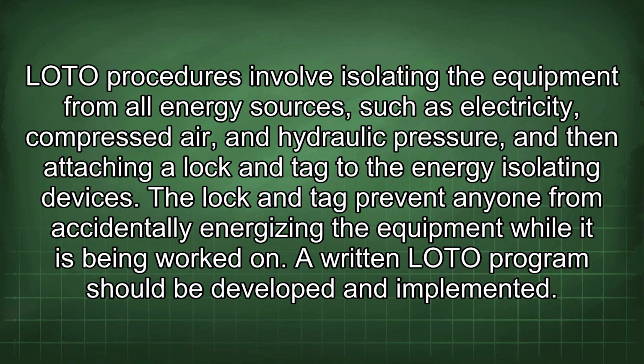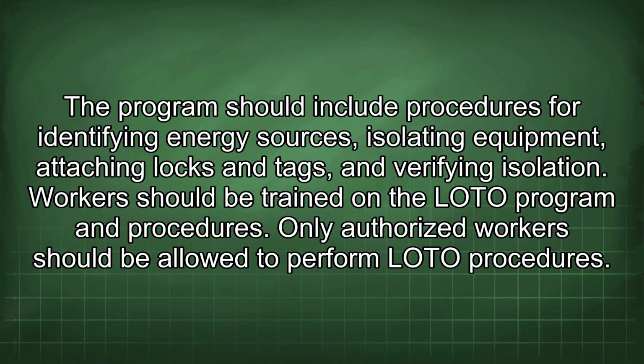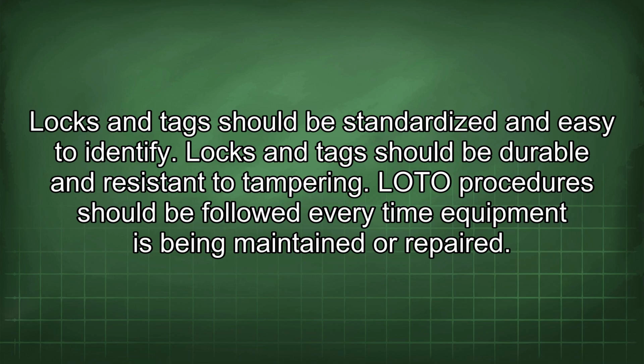A written LOTO program should be developed and implemented. The program should include procedures for identifying energy sources, isolating equipment, attaching locks and tags, and verifying isolation. Workers should be trained in the LOTO program and procedures. Only authorized workers should be allowed to perform LOTO procedures. Locks and tags should be standardized and easy to identify. Locks and tags should be durable and resistant to tampering.